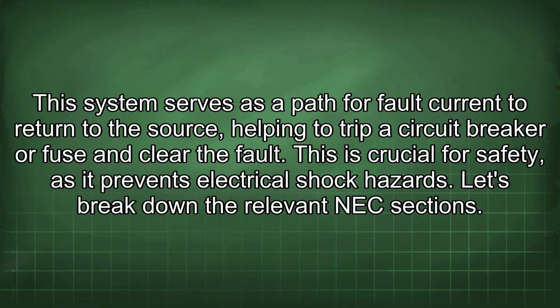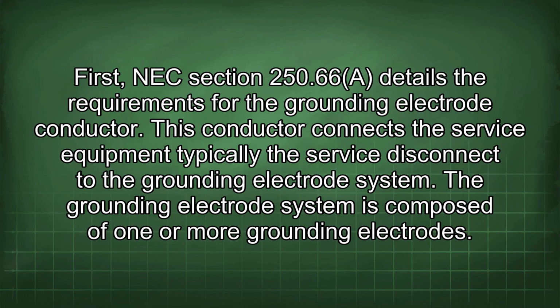This system serves as a path for fault current to return to the source, helping to trip a circuit breaker or fuse and clear the fault. This is crucial for safety, as it prevents electrical shock hazards. Let's break down the relevant NEC sections. First, NEC Section 250.66 details the requirements for the grounding electrode conductor. This conductor connects the service equipment, typically the service disconnect, to the grounding electrode system.